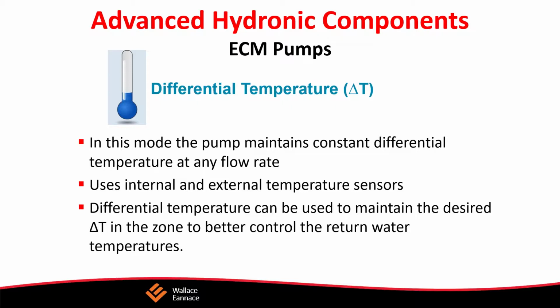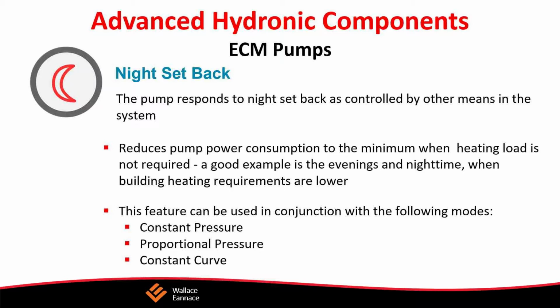Let's take a look at the modes of operation. Once again, we have constant pressure, proportional pressure, constant curve, and night setback. Typically, like I said, in most cases, you're using proportional pressure and constant curve applications.